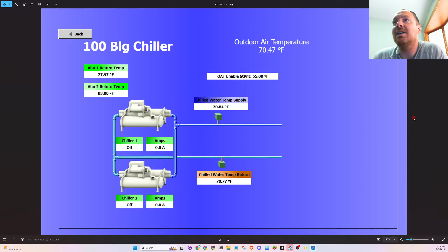So maybe I'm going to ask the AI agent to go over these set points on the graphics here, and then see if it sees any anomalies in the data that we technically would like to see bumped up, if you could get away with it, to 65 degrees Fahrenheit, and that would save you some mechanical cooling runtime on these guys. Unless there's some performance degradation of the air handling units that it can't quite deliver that cooling load, that could help save on some energy bills a little bit.